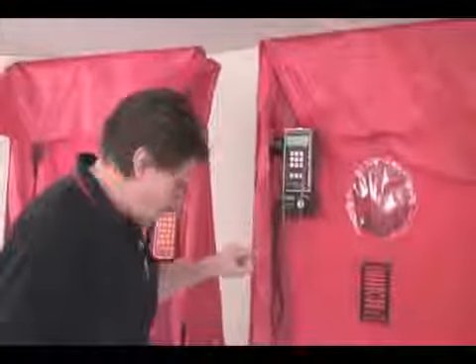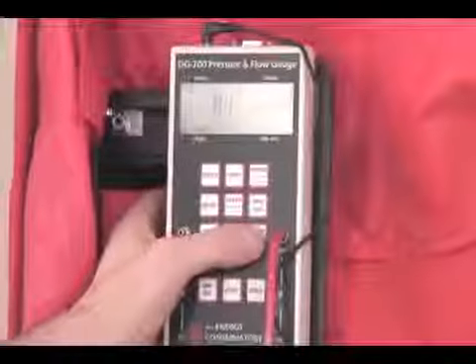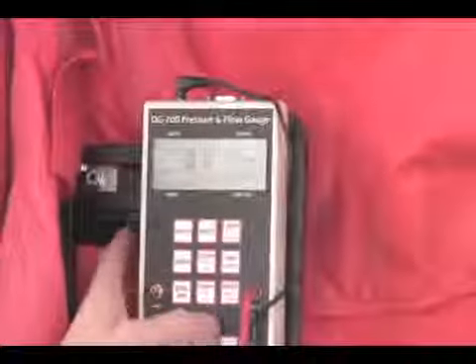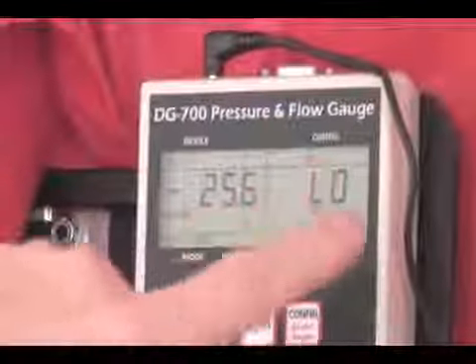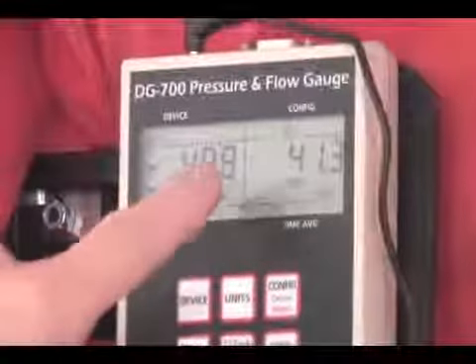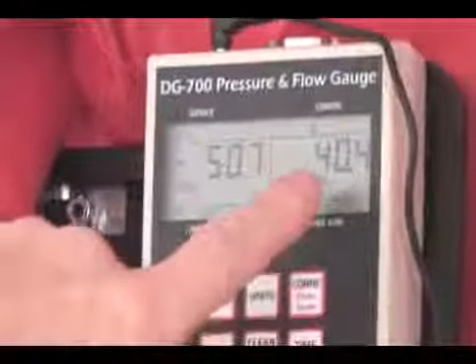So let's take a look and see what we actually measure. We've got a new thing to show you here on this gauge, which is called cruise control. We've got the speed control just barely turned on to set us to the pressure that we want. We go begin cruise, start. You hear the fan starting up. We've already set the mode and the units to leakage area at 50 pascals. It's taking it up to 50 pascals, extrapolating to 50 pascals, and here we have around about 40 square inches of leakage.